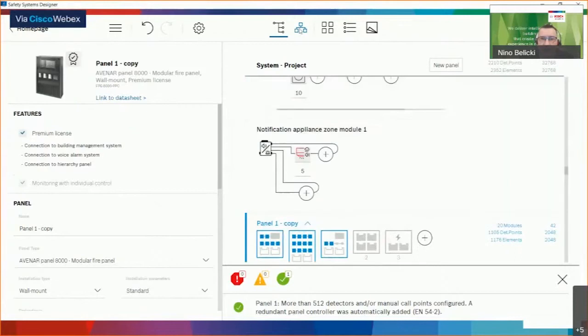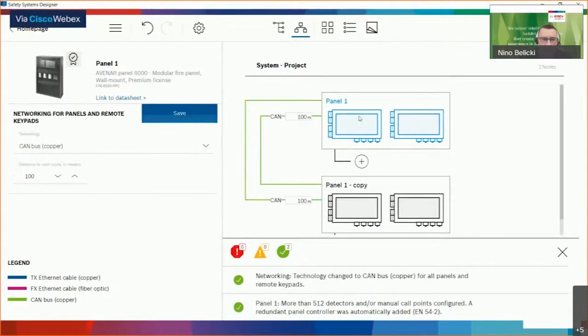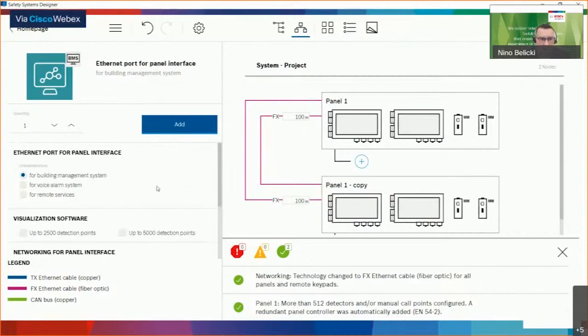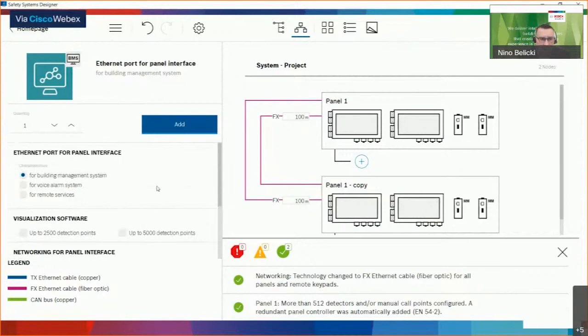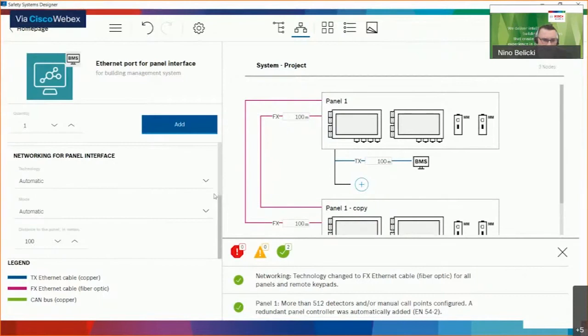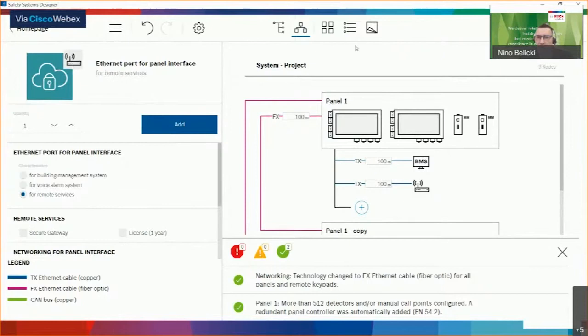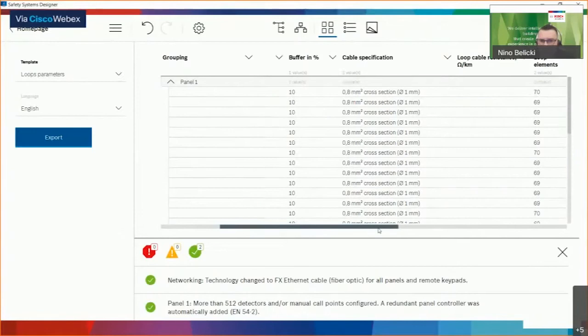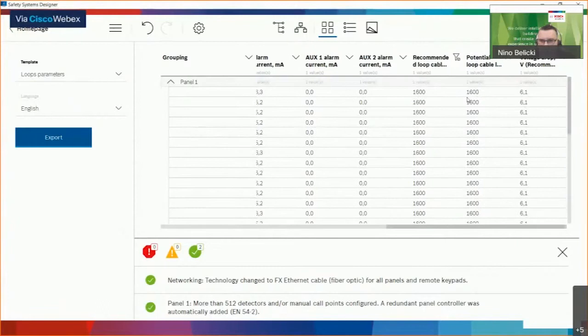In the networking part, you can choose the type of networking. If I go with Ethernet and fiber optics, I get the additional modules needed for that task. We can also add items like BMS or a remote services router — everything remains in the bill of materials list. In this part, you can see templates providing design-regulated items like loop parameters. This is the list of all loops, the loads, cable resistance, and possible loop length with this load. You can also see values when using an auxiliary supply.